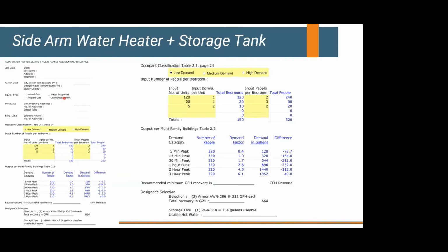Let's look at maybe a sidearm approach, where we're taking a dedicated water heater tied to a storage tank. Now we've got an in-house spreadsheet that takes that ASPE domestic hot water sizing guide and turns it into a usable spreadsheet. So I can plug in that same information we just looked at and analyze it in a spreadsheet form a little bit. And what this is doing is telling us, all right, any place we've got a negative number, we're going to be short of hot water. So that first hour is usually critical to evaluate. Okay, we want to make sure we satisfy this.